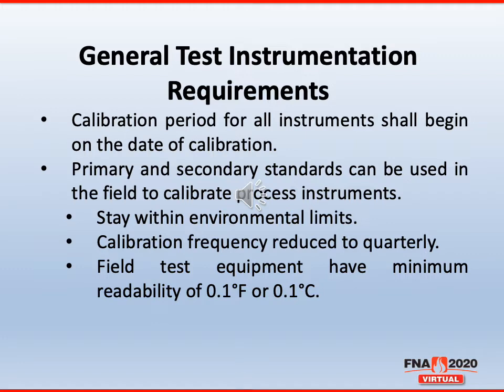Some of the new general requirements when it comes to test instrumentation per AMS 2750F: one thing we addressed was the calibration period for all test instruments, which will begin on the date of calibration. There were some misunderstandings. For instance, if you had 2 test instruments that were calibrated on the same day, but one sits on the shelf in a laboratory and one's being used out in the field, and a couple months later you bring the one from the shelf out into the field, that's actually when your calibration interval would start. And no, we said your calibration interval starts on the date of its first calibration.